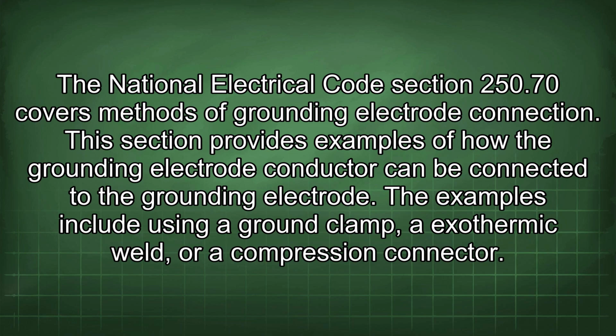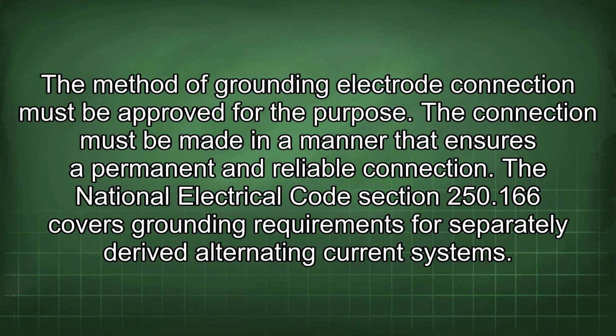The National Electrical Code Section 250.70 covers methods of grounding electrode connection. This section provides examples of how the grounding electrode conductor can be connected to the grounding electrode. The examples include using a ground clamp, exothermic weld, or a compression connector. The method of grounding electrode connection must be approved for the purpose. The connection must be made in a manner that ensures a permanent and reliable connection.